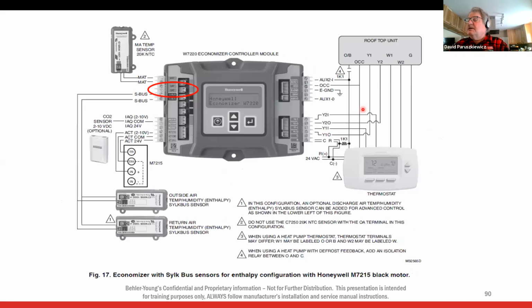All right. So this is how it works. Now, first of all, here's your thermostat. So here's your Y1 goes to the economizer control. Y2 goes to the economizer control. Y2 out, Y1 out, actually come out of the economizer control to the contactors. So what happens if I have first stage call for cooling, it goes to the module, and if the module thinks we can cool with outside air, it locks the compressor out and opens the damper.